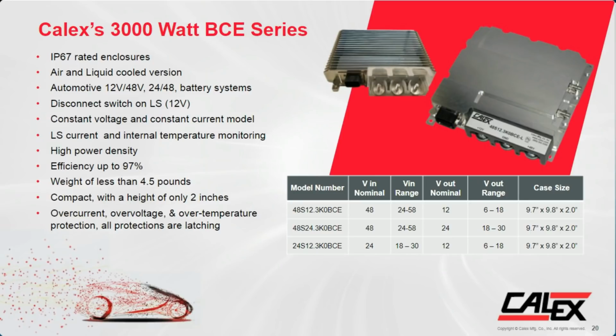From doing industry research and looking at market segments, it looks like the sweet spot for switching to liquid cooling is around 3 kilowatts. I've looked at some of our competitors and test data from engineering, and anything above 3 kilowatts, you're going to have to go liquid cooled. Or in the case of this one at 3 kilowatts, if you're in a harsh environment with no airflow, you'd want to use the enclosure on the right, which is liquid cooled. As long as your coolant is in spec, you can handle 3 kilowatts without derating. So again, high power density, small size on these.